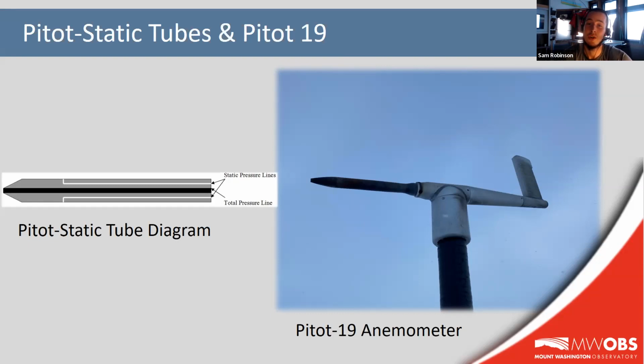These two lines, the total and static pressure lines, are then connected to the pressure transducers or sensors down in our weather wall, which then effectively determines that differential pressure and is able to convert it into an electrical current. That electrical current is then converted through a data logger, which also takes into account temperature and atmospheric pressure to the useful information that we want and need, which is the actual velocity or speed of the wind.